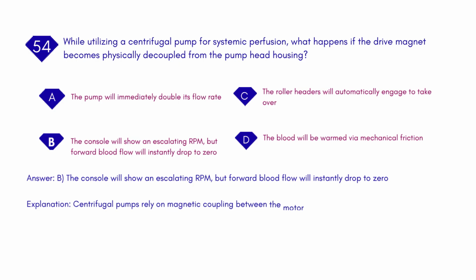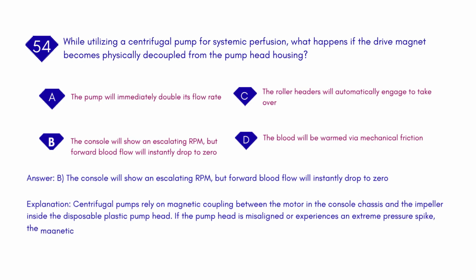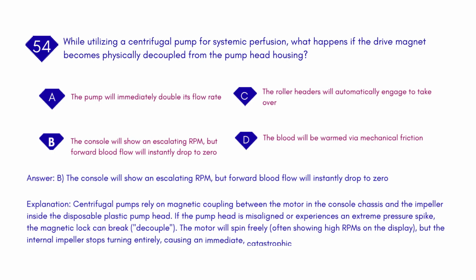Explanation: centrifugal pumps rely on magnetic coupling between the motor in the console chassis and the impeller inside the disposable plastic pump head. If the pump head is misaligned or experiences an extreme pressure spike, the magnetic lock can break, decouple. The motor will spin freely, often showing high RPMs on the display. But the internal impeller stops turning entirely, causing an immediate, catastrophic loss of forward blood flow.